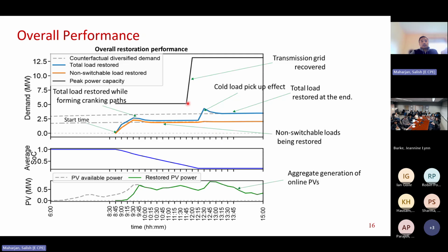At the 12 to 12:15 transition, you can see that there is an augment in the total capacity. It's because of the recovery and connection with the transmission grid. And you can see that in the total load, there is a surge in the load pickup because the transmission grid is connected and we are able to pick up all the non-critical or switchable loads. And you can see that there is a gradual decrease in the load as shown here. It's because of the cold load pickup effect.